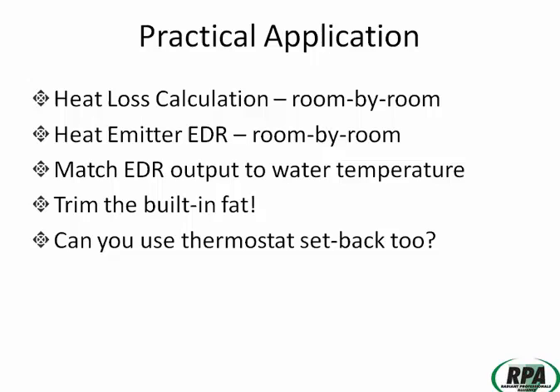So can we use thermostats with setback as well? And with the new boilers, we can. Next slide, or next click, Mark. A lot of the new boilers have a feature called boost, which lets us tell how long we want it to wait before boost kicks in. What boost does is allow us to program in a higher water temperature than the outdoor reset curve would call for, and allows us to use setback thermostats and come back from deep setback with modulating condensing boilers and with a well-adjusted outdoor reset curve.